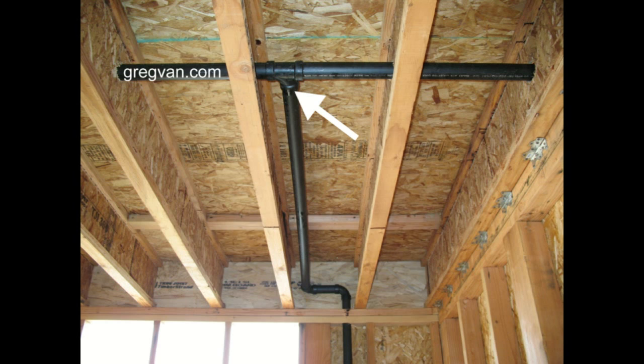Sometimes a picture is worth a thousand words. This same slope of a quarter inch per foot, quarter inch per linear foot, will apply to a vent pipe and to a drainage pipe. This would be anything three inches and less.